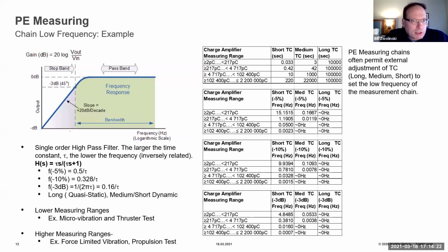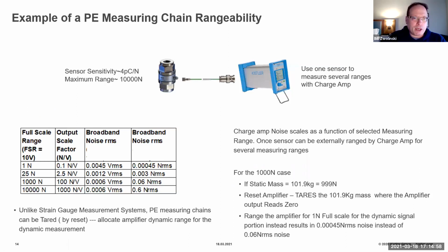So in a piezoelectric, you're usually dealing with something that's AC coupled, and even in quasi-static measurement, you're eventually going to not be able to measure anymore over time. It's going to have a limit eventually. So for short duration and medium duration events, piezoelectrics are widely used. Some applications: micro vibration and thrust tests. Certainly, force limited vibration and propulsion test is another application that we often come across. The rangeability that I talked about.